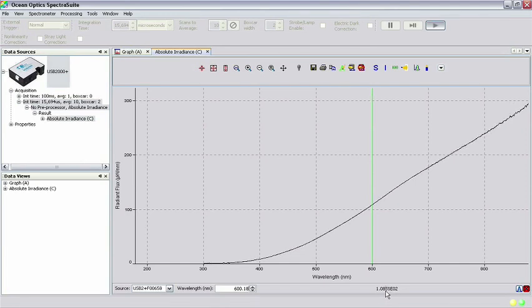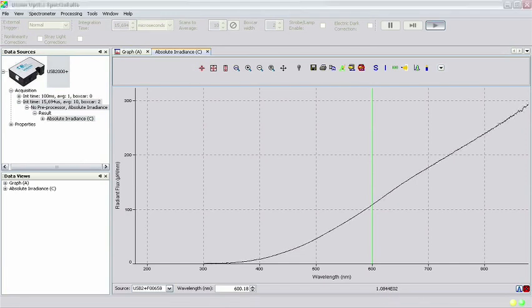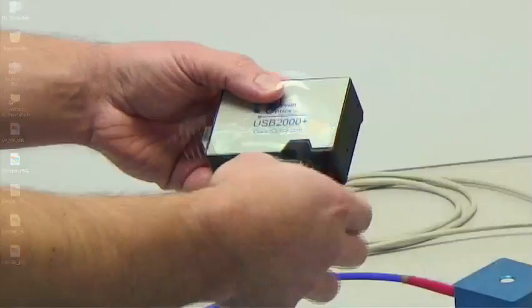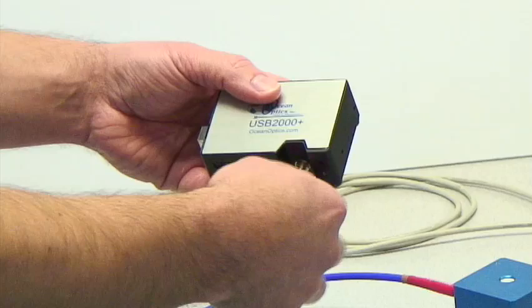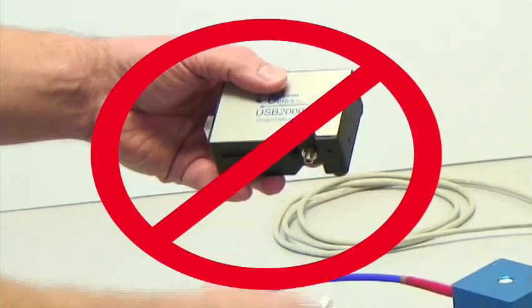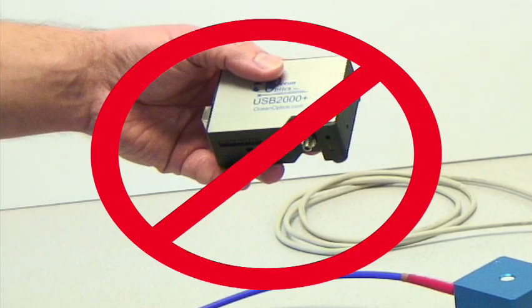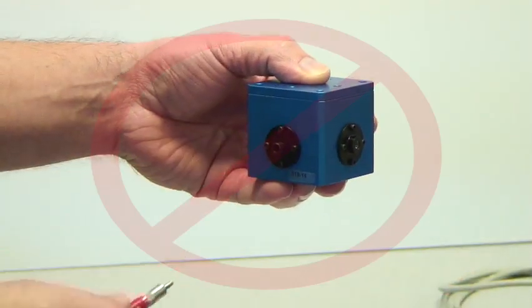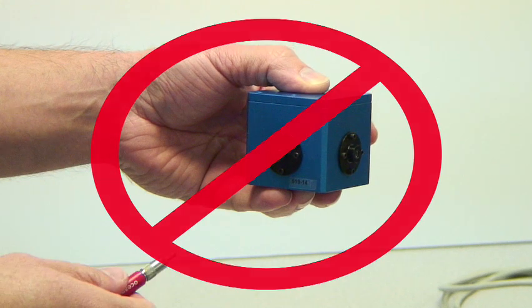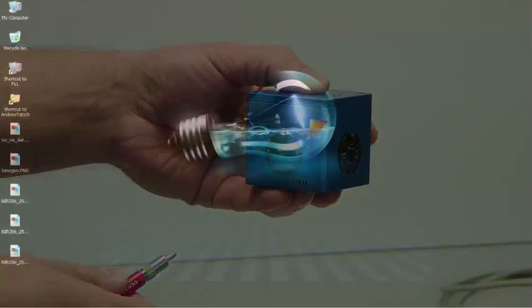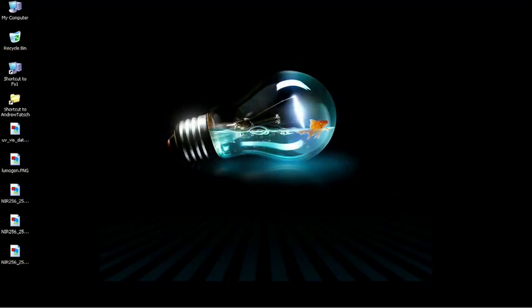Once your system has been calibrated, you do not need to recalibrate the system each time you wish to take a measurement, provided you have not removed the fiber from either the spectrometer or the integrating sphere, and you do not drastically disturb the orientation of the fiber. You have calibrated the fiber, spectrometer, and integrating sphere as a system, so any alterations to the system will mandate a recalibration.